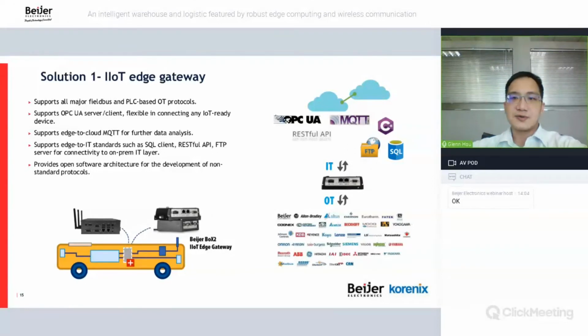Other than the PLC protocols, we support a built-in OPC UA server and client, which gives you the flexibility to connect the Edge Gateway to any IoT-ready devices that also have OPC UA built in. For connectivity to the cloud, we support MQTT to publish data over a secured channel. For connections to on-prem IT, we have SQL clients, RESTful API, and FTP server available. And if any of the above protocols are unsuitable, our open software architecture allows you to create a tailor-made communication for your own use.